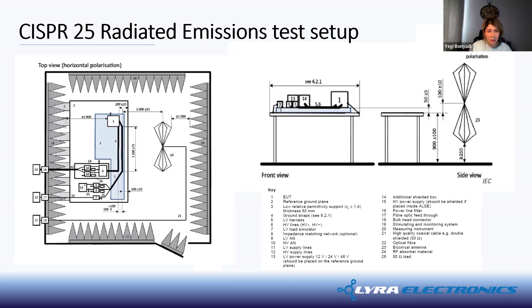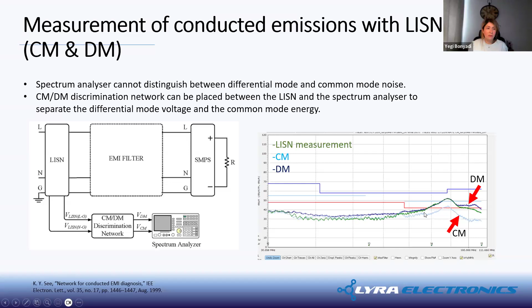Okay, so spectrum analyzers are normally used to measure the emissions, but they cannot distinguish between common mode noise and differential mode noise. In this slide, I'm showing you the difference if you use a discrimination network between your LISN and the spectrum analyzer. You can separate common mode from differential mode noise. So in the graph on the right-hand side, you can see how this is shown. It does help a lot when you're trying to troubleshoot your device. If you're failing, for example, in this case, between, let's say, 80 to 100 megahertz, you can just separate them to know if it's more common mode noise or differential mode noise, and then design your filters according to that.